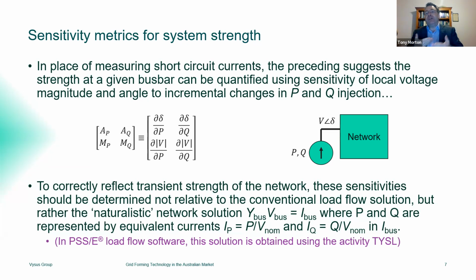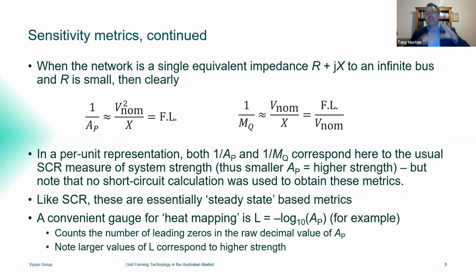And the way that we look at this is we determine the sensitivities not from the conventional load flow solution where we have fixed P and Q and fixed voltage magnitudes, but we actually go right down to the basic circuit equations, the YV equals I equations from the system admittance matrix, and determine the sensitivities that way. And we can actually use power system analysis software to drill down directly into that picture and get those sensitivities from a basic modified type of power flow. And when we do that, there are essentially 4 coefficients, because we can look at the sensitivity of magnitude and angle, and we can look at the sensitivity to changes in active power or reactive power. And the 2 key ones there are the one we call AP, which is the sensitivity of angles to active power, and MQ, which is the sensitivity of magnitudes to reactive power.